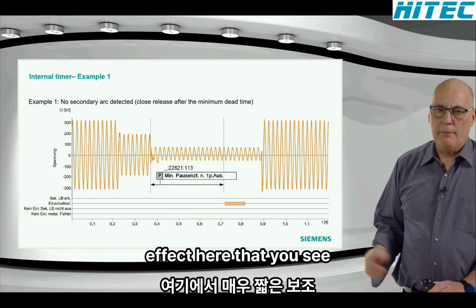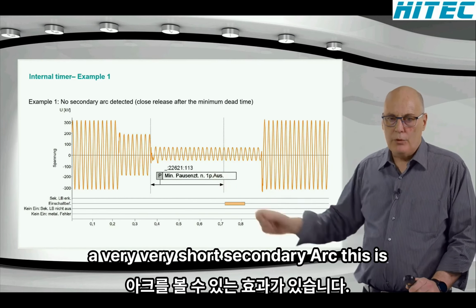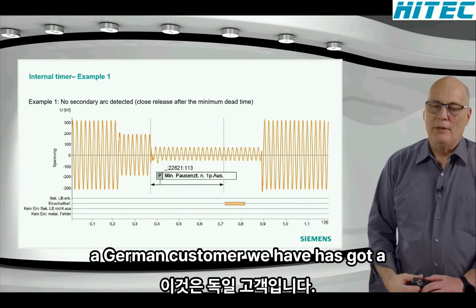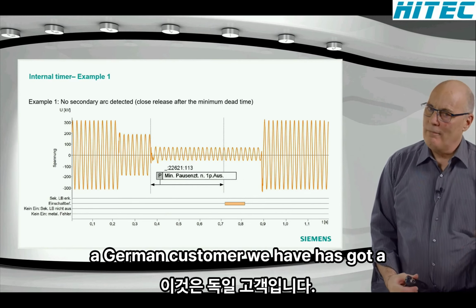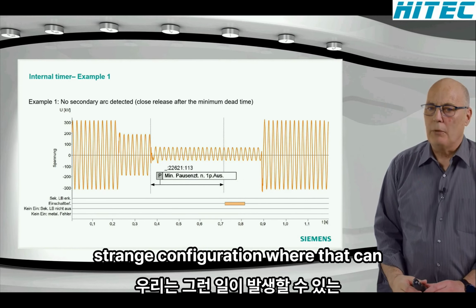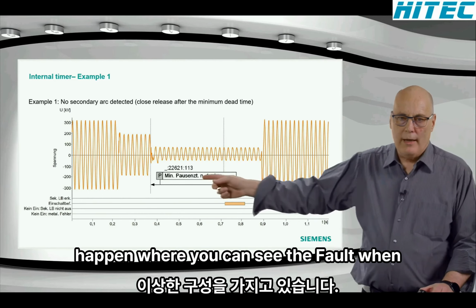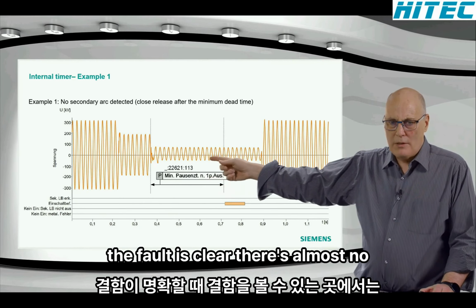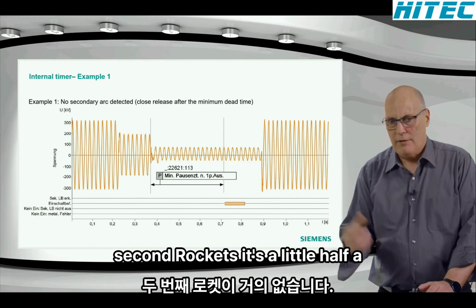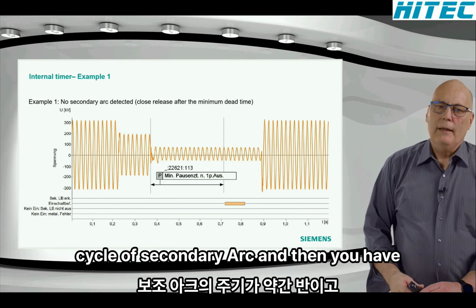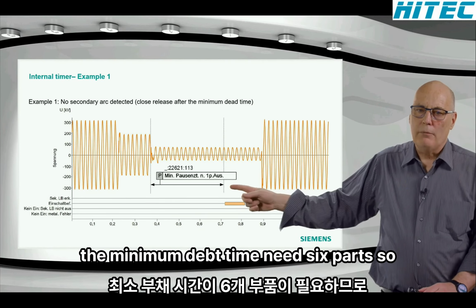effect here that you see a very, very short secondary arc. This is a German customer we have. He's got a strange configuration where that can happen, where you can see the fault, when the fault is cleared, there's almost no secondary arc. It's half a cycle of secondary arc, and then you have the minimum dead time needs to expire.